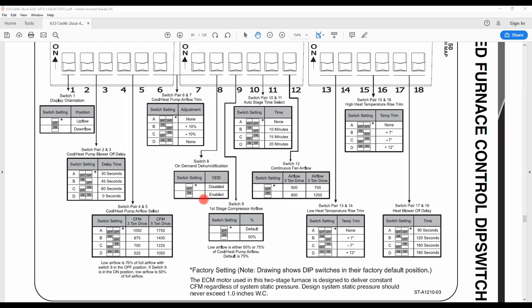Just know you can turn that to on position to enable dehumidification, which then slows down your blower speed. Number 9, you're going to see, we talked about that first stage compressor airflow. That works in series with number 4 and number 5. You'll then find dip switch number 10 and 11. So now we're getting more into the heating side of the airflow. 10 and 11 are only used if you have a single stage thermostat. So if you have a single stage thermostat and you want a time between stages, then you will set dip switch 10 and 11.